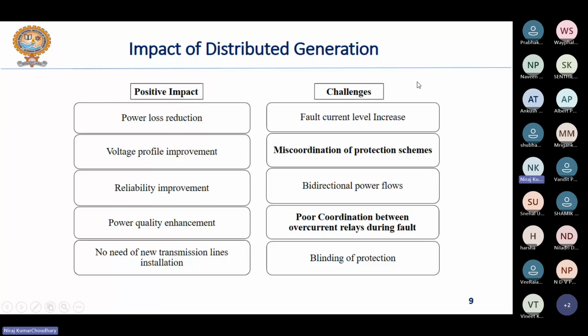So along with the several positive impacts, you obviously have certain challenges. These are basically operational challenges, such as the increase in fault current levels. Then you may have bidirectional power flow in the system, which may cause different protection coordination challenges in terms of blinding of protection or false tripping of certain parts of the system. Then there may be the problem of unintentional islanding.